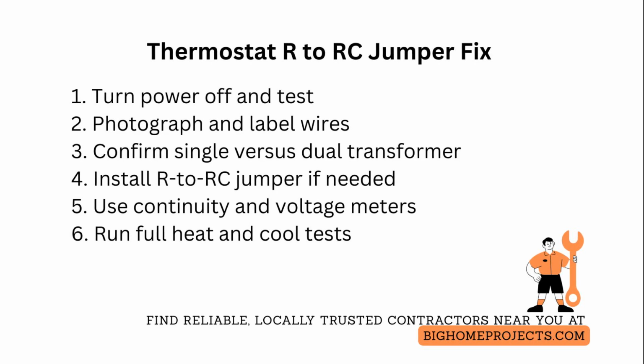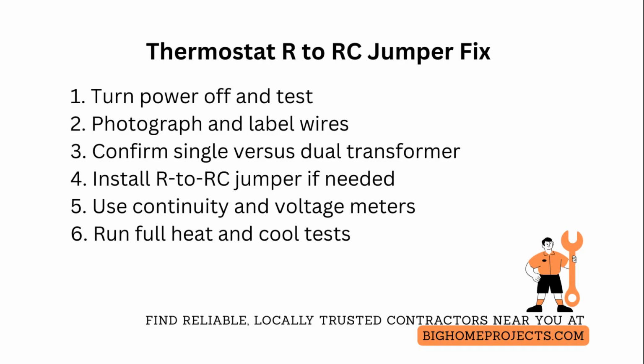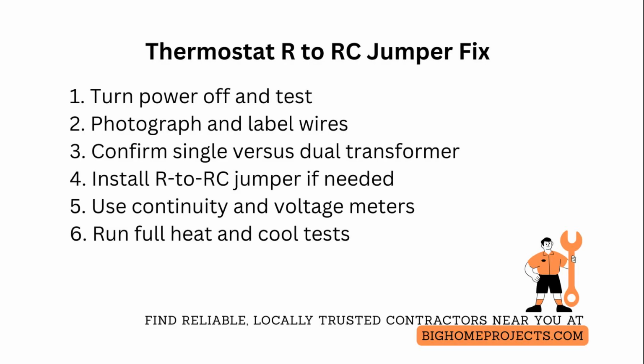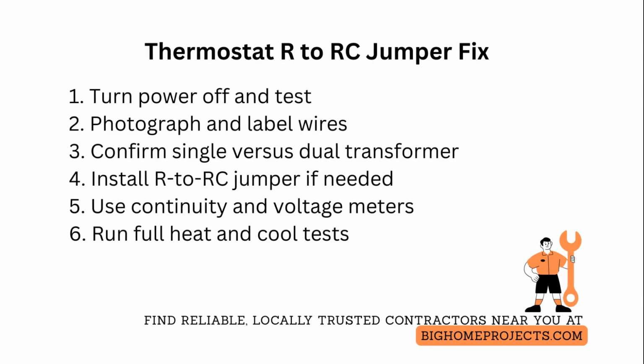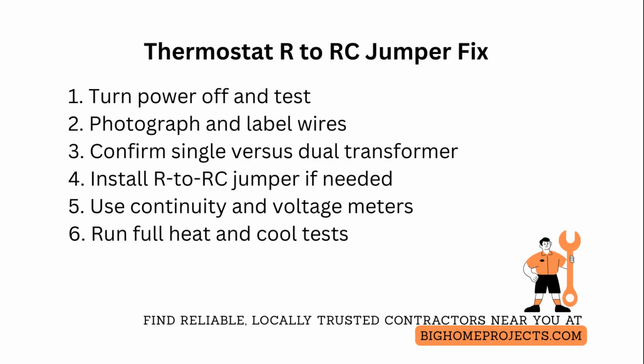For smart thermostats that expect separate R and RC inputs, supply a proper jumper or install a common wire adapter per the manufacturer's wiring diagram. When in doubt, consult the furnace or air conditioner's wiring schematic because forcing a jumper across incompatible transformers can damage equipment. Finally, after wiring and powering up, monitor system operation for at least one full cycle of both heating and cooling and document voltages at R, C, Y, and G during calls to make future troubleshooting faster.